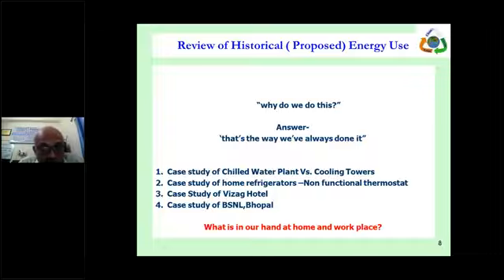Then when we checked separately, if I operate this one, what is the energy consumption, and if I operate the other one, what is it? These people thought the 100 kilowatt motor would consume less, so they were using that 100 kilowatt compressor more, and the other one was kept on standby.